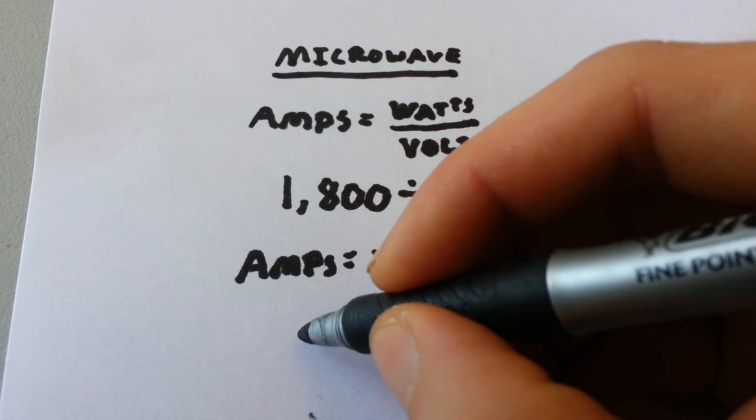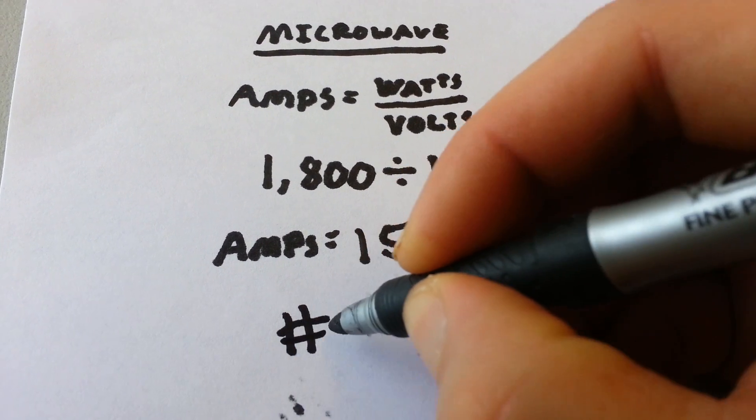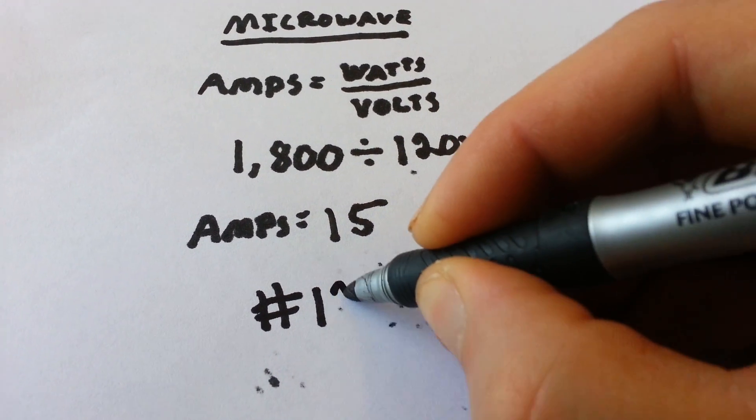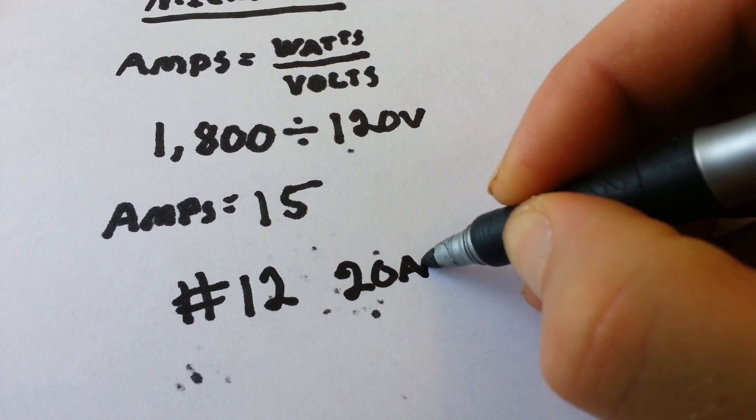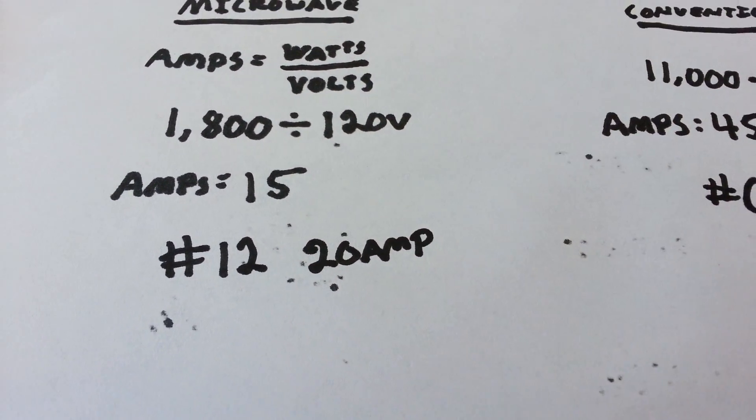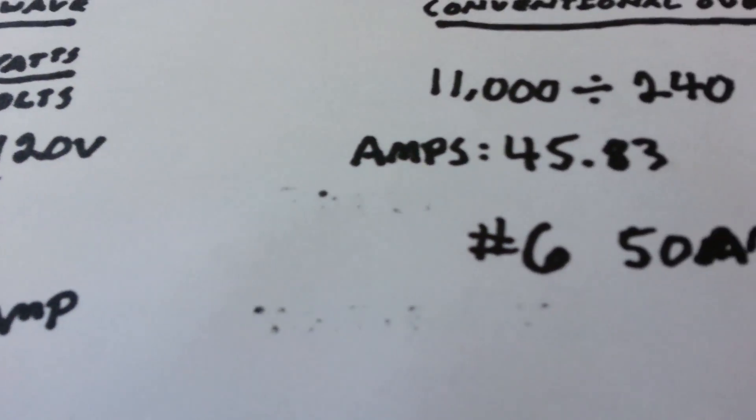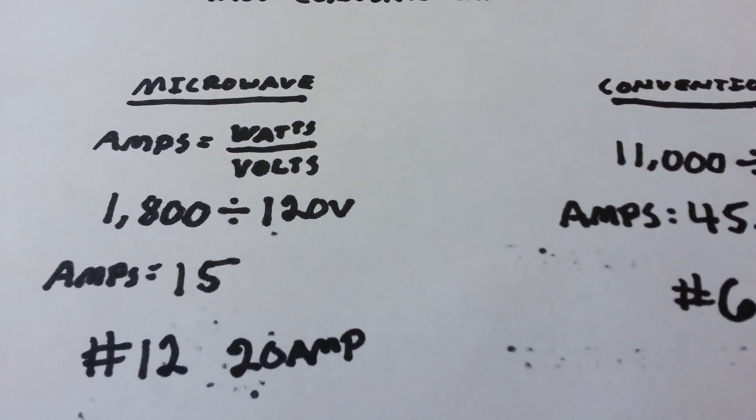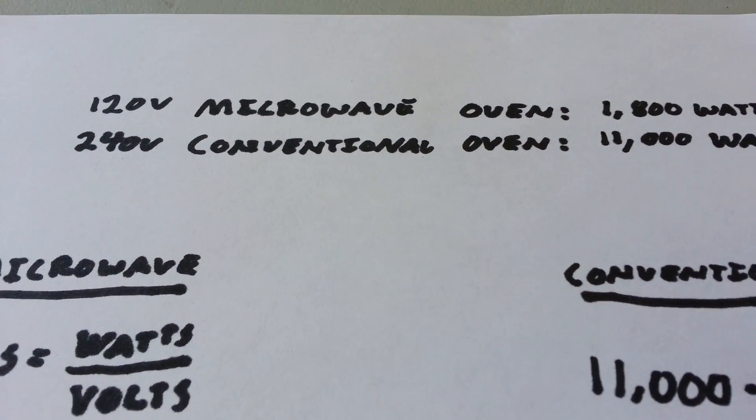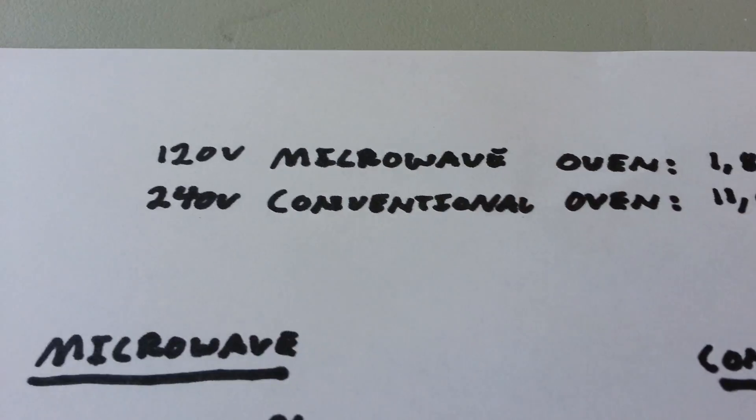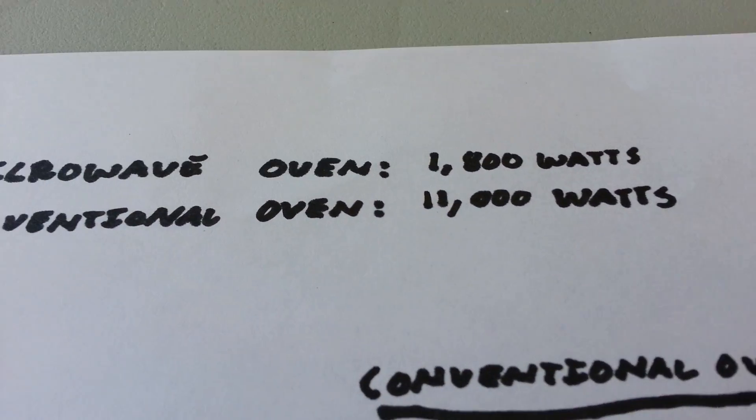For the microwave, we would run number 12, and it would be a 20 amp. And that's how it's done. It's pretty simple. It's all about looking at the equipment itself and being able to determine the voltage and the wattage.